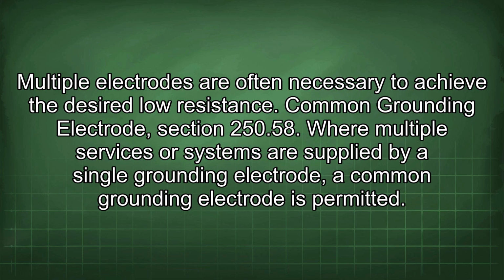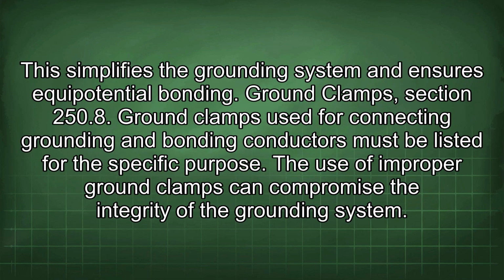Common grounding electrode, section 250.58. Where multiple services or systems are supplied by a single grounding electrode, a common grounding electrode is permitted. This simplifies the grounding system and ensures equipotential bonding. Ground clamps, section 250.8. Ground clamps used for connecting grounding and bonding conductors must be listed for the specific purpose. The use of improper ground clamps can compromise the integrity of the grounding system.